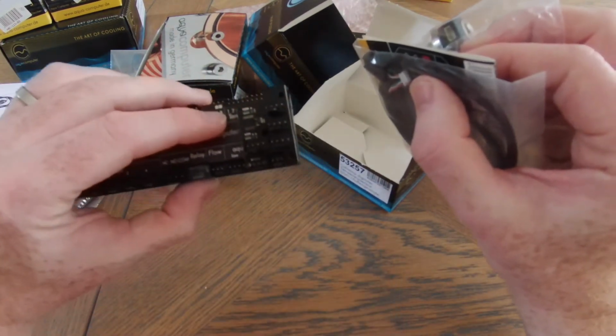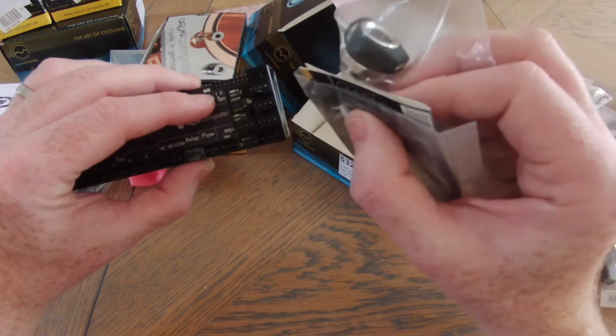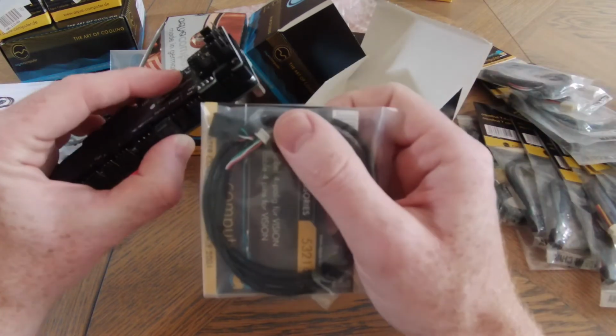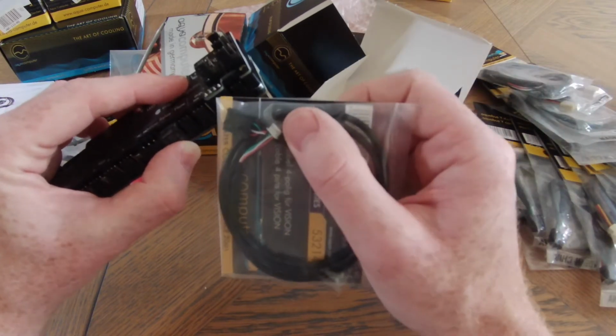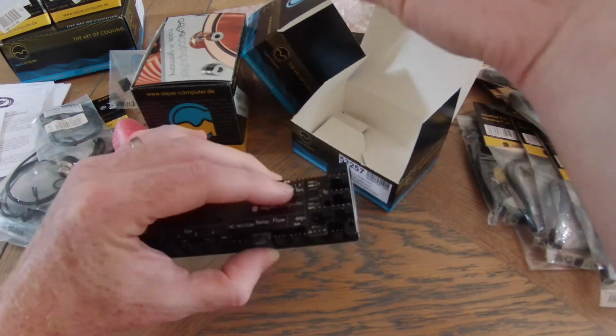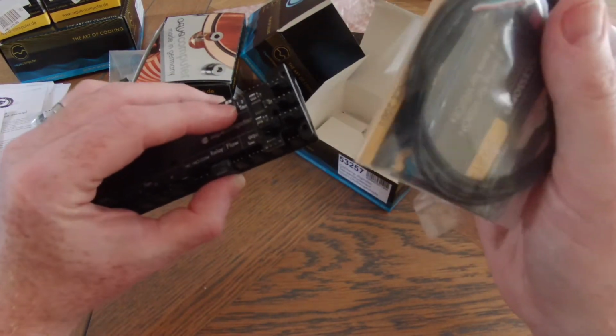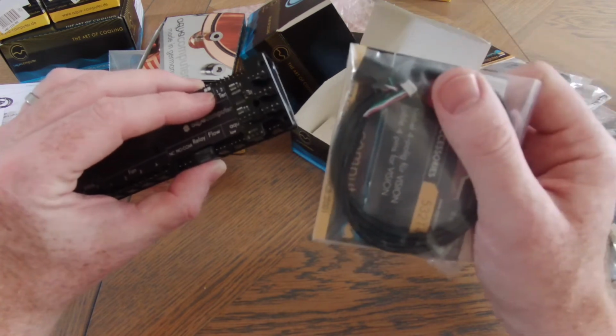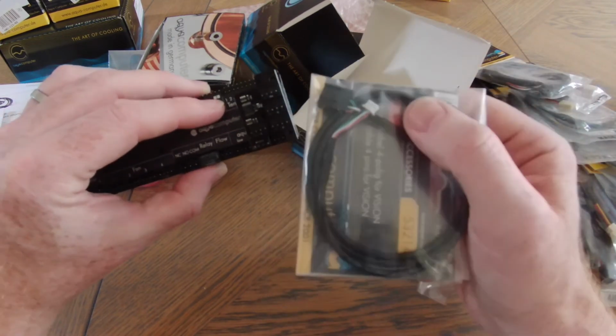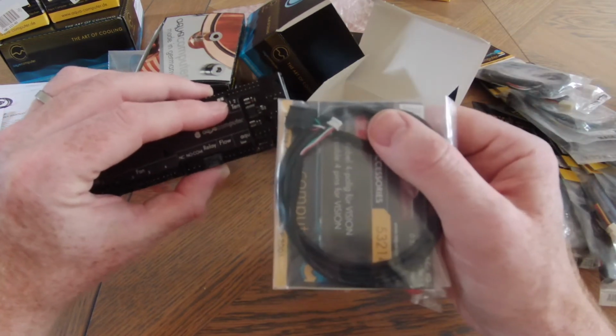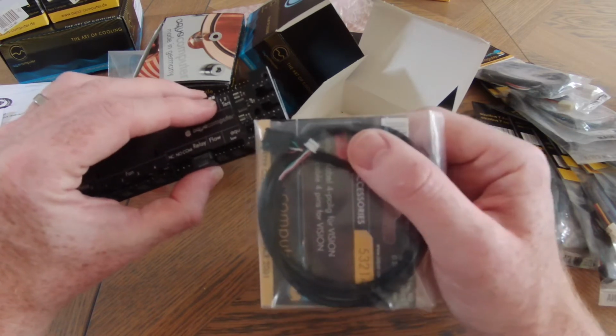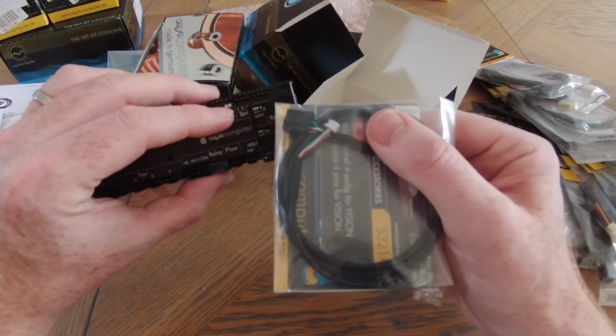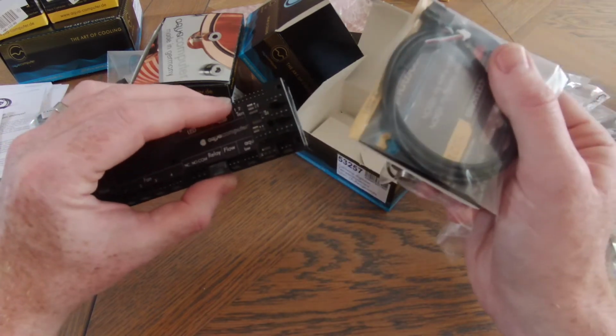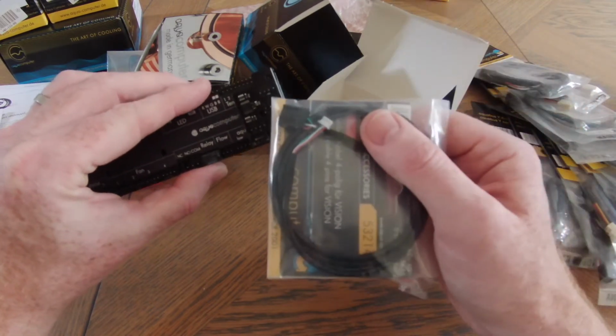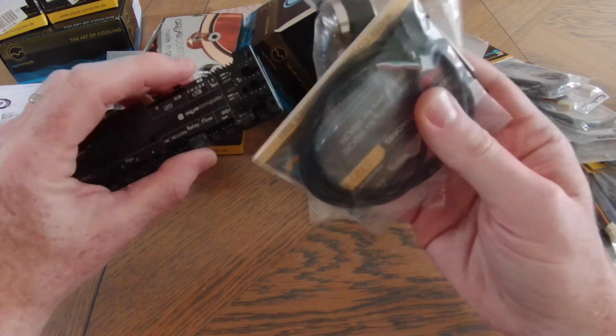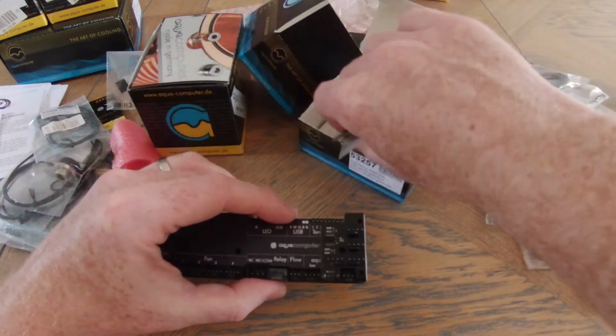But I don't believe you can connect more than one of these per channel. So if I just had one connection on my Aquaero and then split it using a Splitty 9, this wouldn't work. It needs a clean channel connection. So you need to use this X4 board because that now is effectively 4 distinct Aquabus channels. So I could daisy chain off that one and connect other components which do support daisy chaining, but then I've got 1, 2, 3 connections left for a direct connection to these CaliTemp sensors.